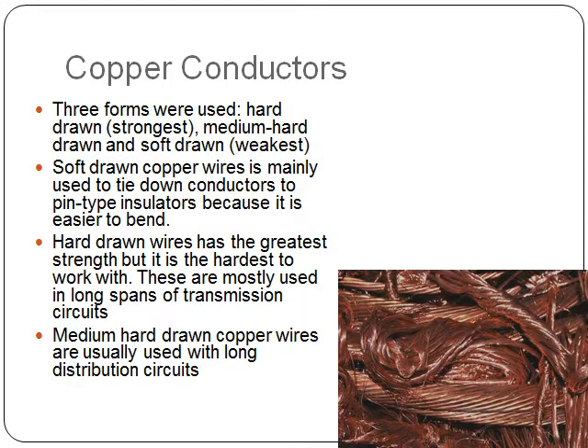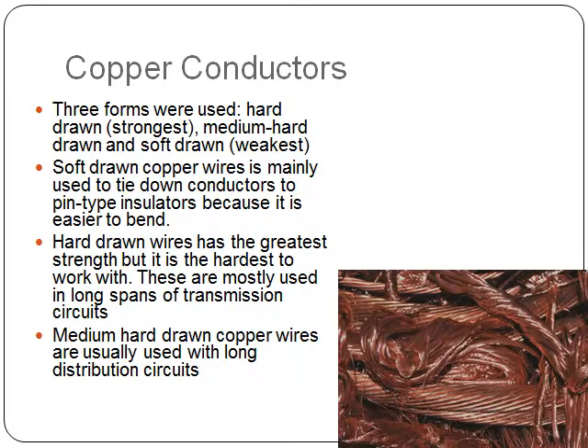There are three forms of copper conductors used. They are Hard Drawn, which is the strongest of the three; Medium Hard Drawn; and Soft Drawn, which is the weakest. Soft Drawn copper wires are mainly used to tie down conductors to pin-type insulators because they are easier to bend. Hard Drawn wires have the greatest strength but are the hardest to work with, and are mostly used in long spans of transmission circuits.